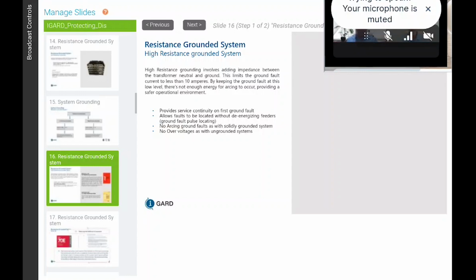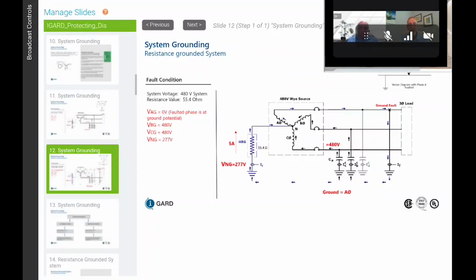Remember, if we go back to this slide over here, when you get a ground fault, the unfaulted phases are going to elevate to the full line-to-line potential. But if you have a lot of current flowing through your resistor or reactor, you're not going to get this over voltage that occurs on the unfaulted phases. So that's the main difference between a resistor and a reactor. A reactor will limit the over voltages because you've got so much current flowing through it. And the resistor, if you have a lot of current flowing through it, you're going to get higher voltages because of the X over R ratio.